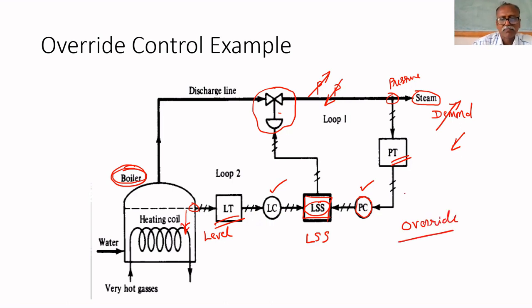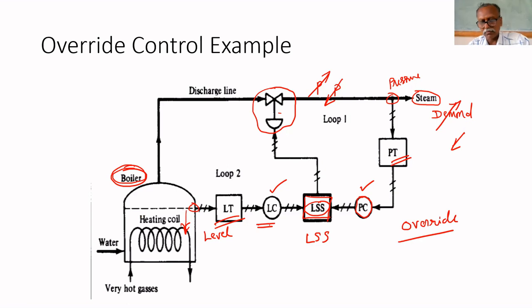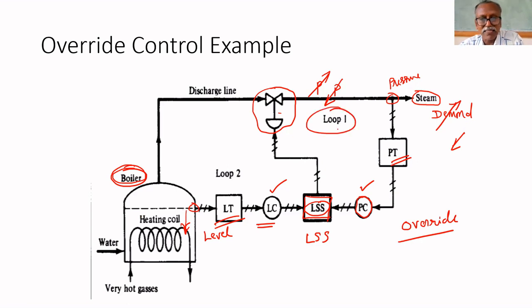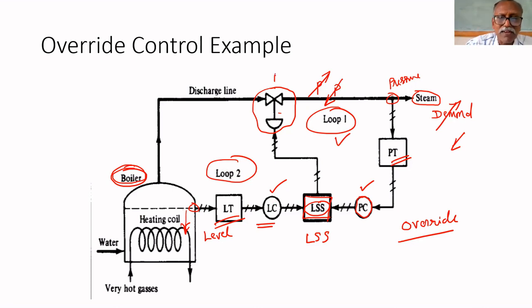It overrides the other — whichever is less will be selected. This LSS selects the lower value among the two signals. If pressure is less, loop 1 will work; if level is less, loop 2 will work. There is only one manipulated variable but two measurements — similar to cascade control.